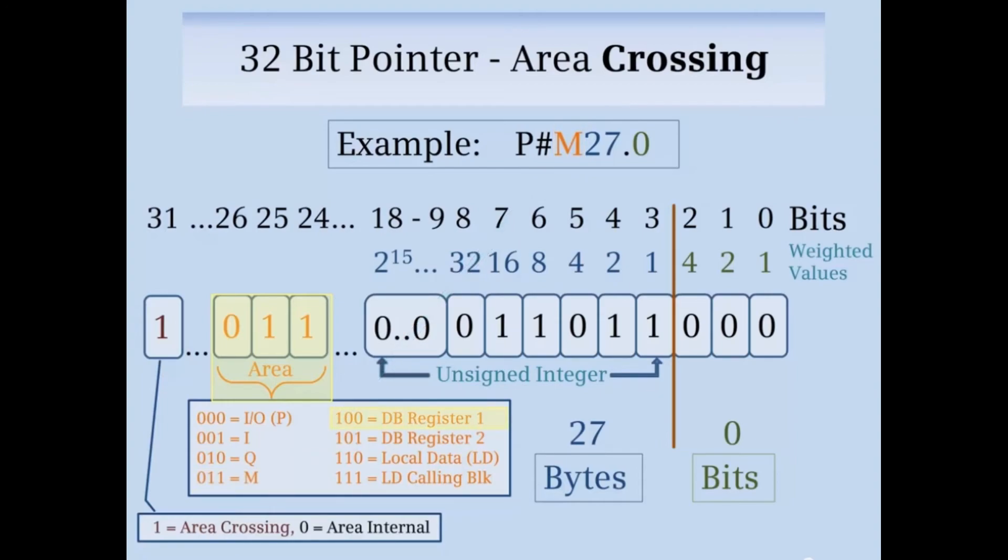100 is the data block area in DB register 1, which is a global DB. 101 is the data block area in DB register 2, which typically is a data instance block but can be a global DB if the programmer has intentionally loaded a global DB in DB register 2. 110 is local data in the interface area of a block. 111 is the local data area of a calling block.